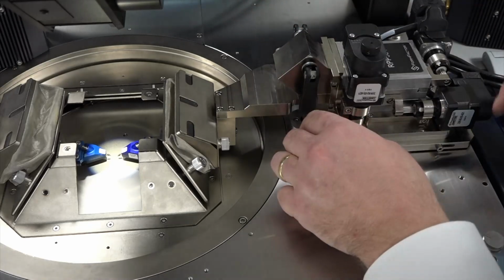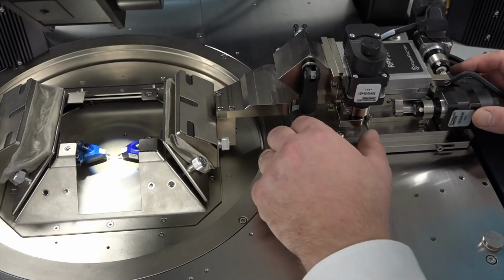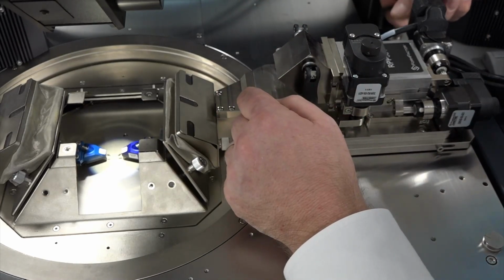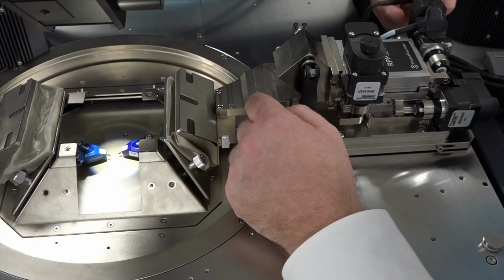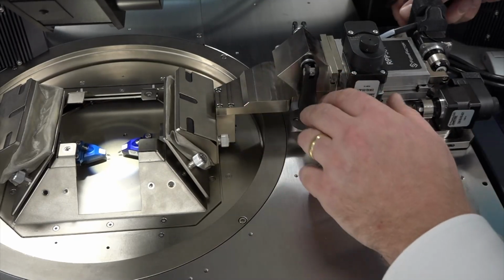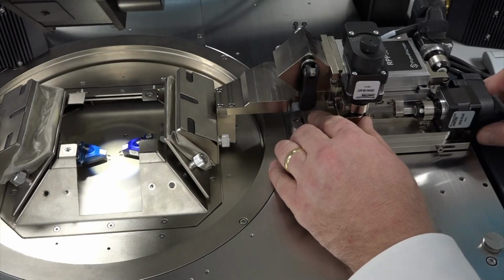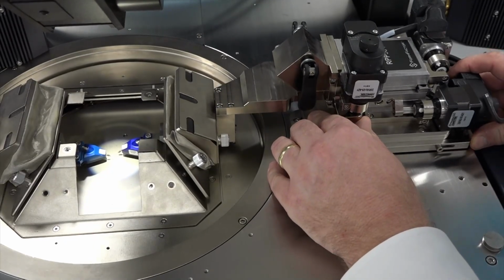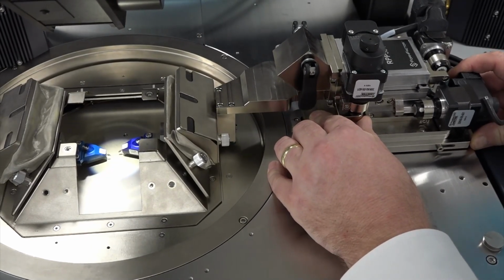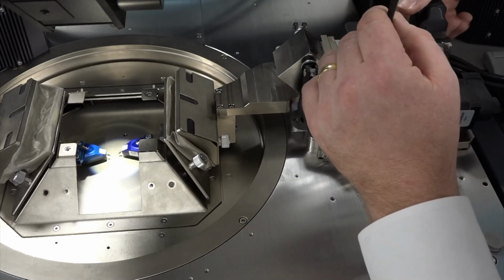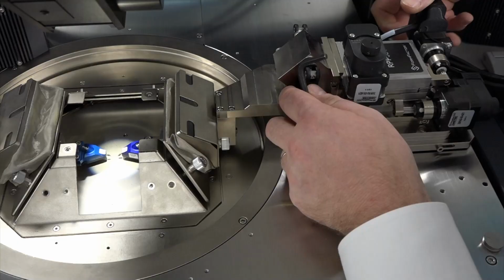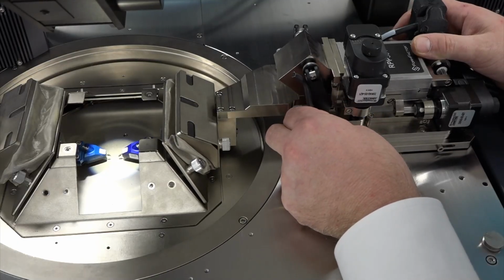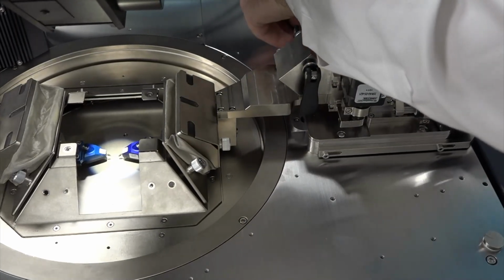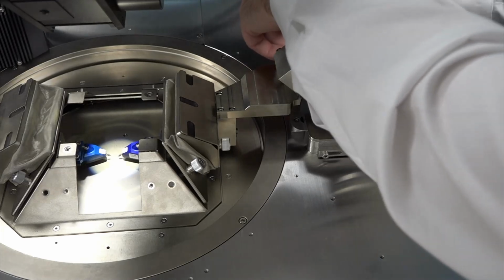But if I wanted to, I could slide the base of the positioner backwards and forwards. If you ever do slide the base of the positioner, do this: move the probe in Y, so that if you slide it, you're not going to slide into the opposite probe. So if you see me, I can put my hands, make a little adjustment like so. Just make sure I didn't move to anywhere silly. And then I'll lock the thing in place. Make sure you don't put any load on it because it might move a tiny bit.